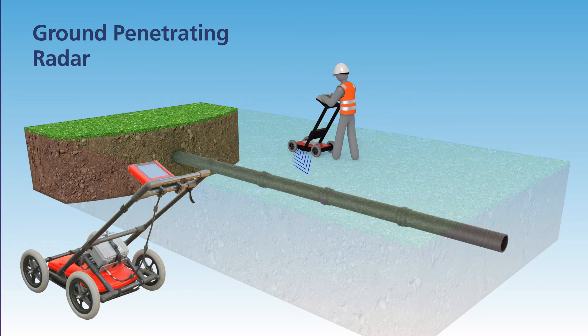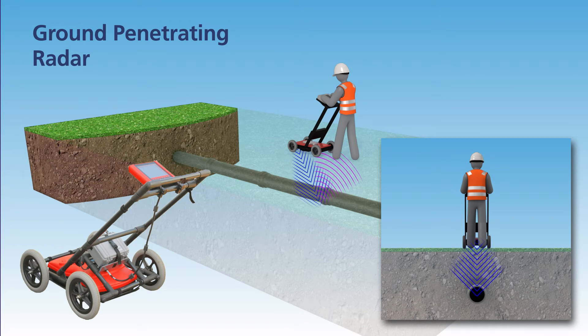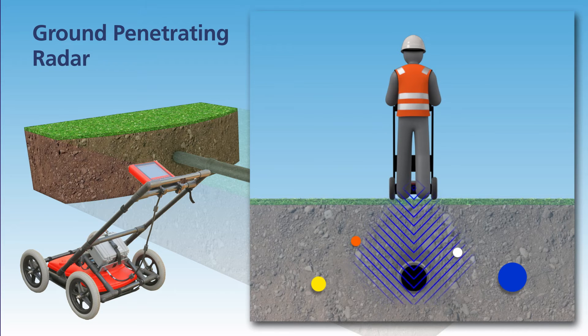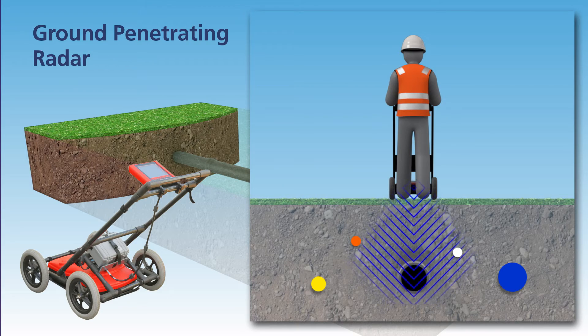The electromagnetic field is then detected using a receiver. Ground penetrating radar uses radar pulses emitted into the ground. When these pulses strike a change in the subsurface, like a pipe or cable, they are reflected back to the radar unit and the results are displayed on a screen for the operator to interpret. If you are using your own locating equipment, ensure the operators are trained in how to use it and aware of its limitations. The equipment must be calibrated and capable of detecting all types of cables and pipes. Some locating equipment may not detect an electric cable unless there is current flowing through it, and may not be able to detect non-metallic pipes or cables.